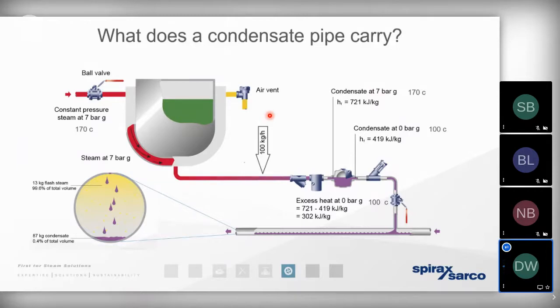So we know that when steam gives up its heat energy and condenses, it changes state from gas to a liquid. We know there's a volumetric change, but there isn't a mass change. 100 kilograms of steam is 100 kilograms of condensate. We know that when steam condenses, it doesn't give up its temperature. In other words, the condensate that exists in the pipework that's been drained away from the bottom of the heat exchanger has the same mass flow rate, the same temperature, and the same pressure. The only difference is it exists as a liquid rather than as a gas.